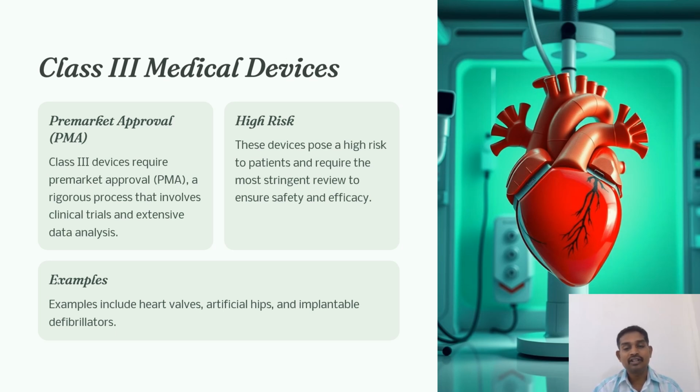which pose a high risk to the patient, so they require the most stringent review to ensure safety and efficacy. Equipment such as heart valves, artificial hips and implantable defibrillators require pre-market approval, which is a rigorous process that involves various clinical trials and extensive data analysis.